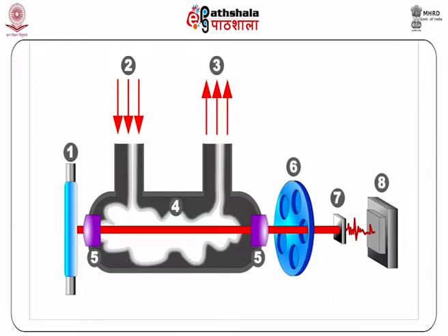The device contains a source of IR radiation, like a lamp, generating an IR beam. The IR beam is made to pass through the chamber containing the sample and is then focused on a rotating filter wheel with the help of a lens.